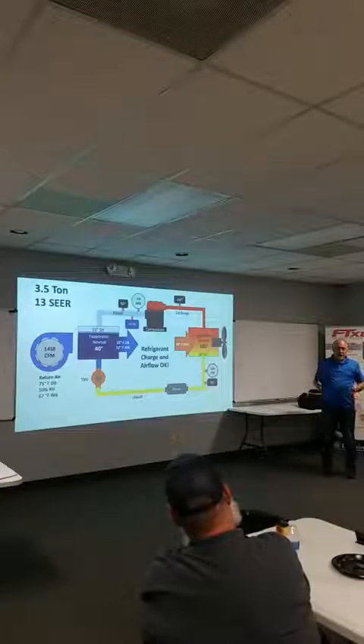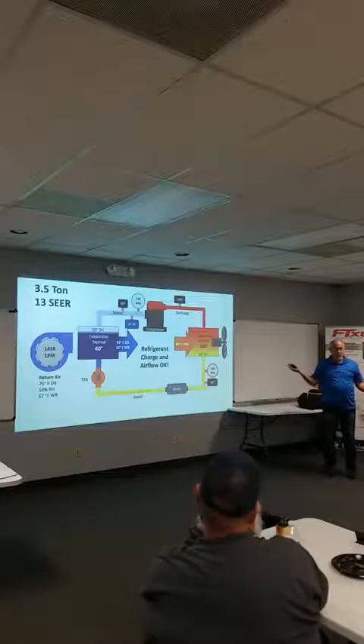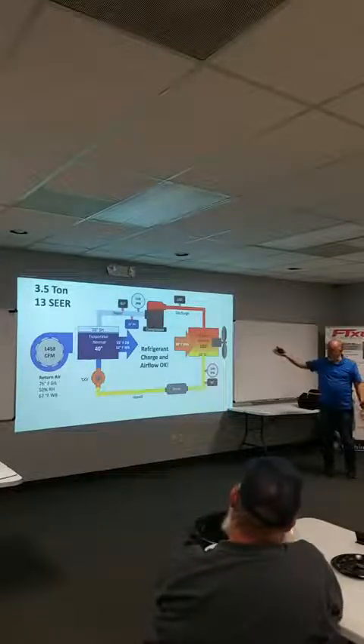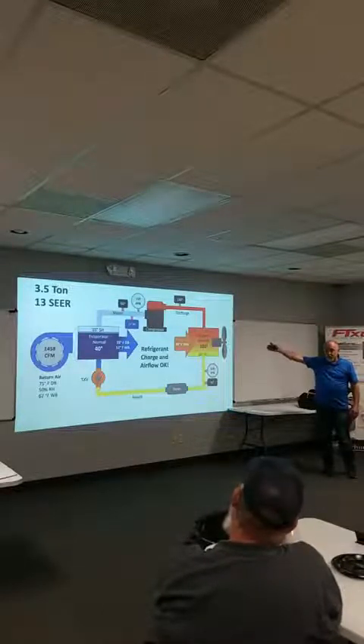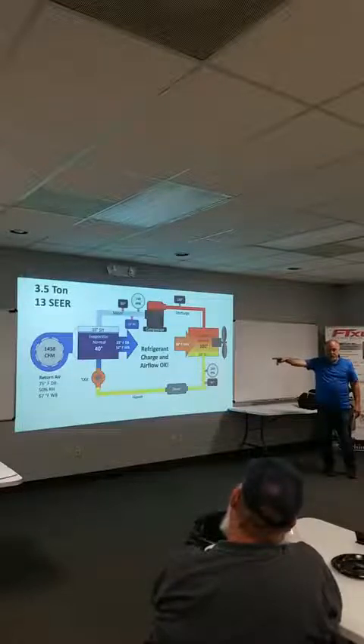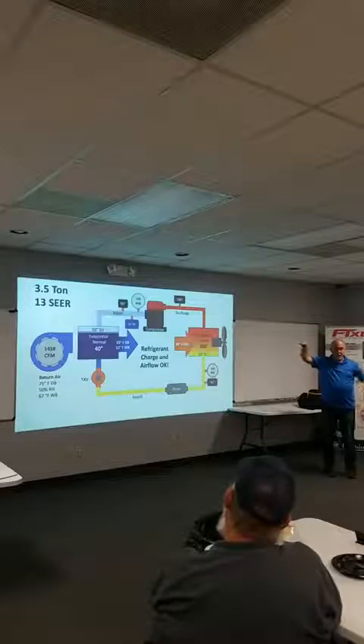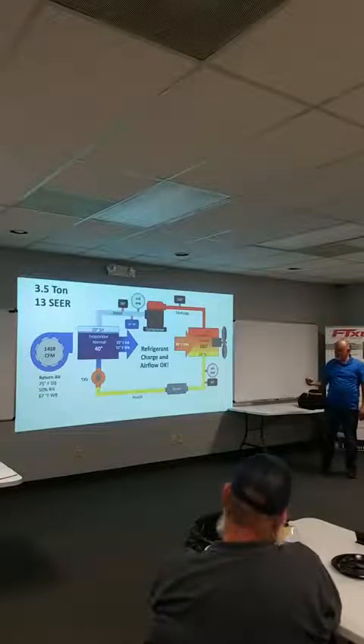So this is why, when you go outside when it's cold, and you're trying to do a cool weather inspection, it's really hard because all the refrigerant's in the wrong place in the system, and it takes a long time to get all that refrigerant through that condenser, through that little tiny metering device hole, and up into the evaporator where it goes and stabilizes. So it takes time for that refrigerant to balance in the system. We're always chasing that refrigerant around in that system, right?